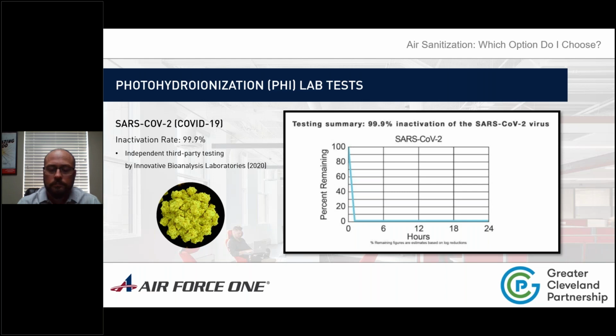So with that said, the reason this test has a ramp up time is because, as Austin pointed out, there was a nebulized CoV-2 in the chamber, and then they turned the PHI on, and because of the volume and the saturation level, it took between 1 and 2 hours to get to a zero, but the 99.9%. Once you're there, it continuously stays.